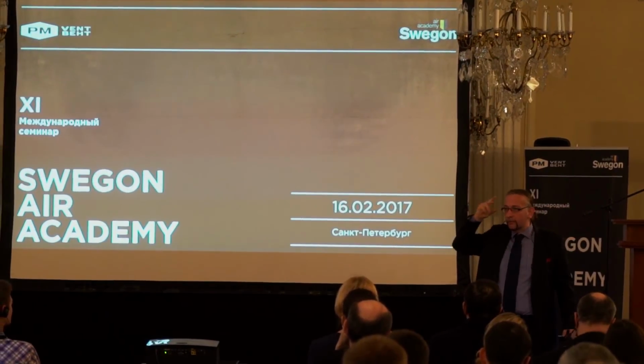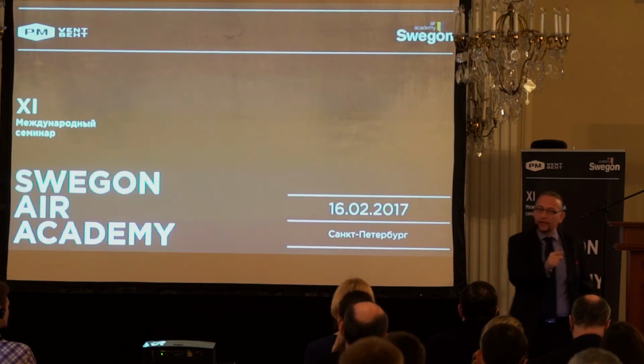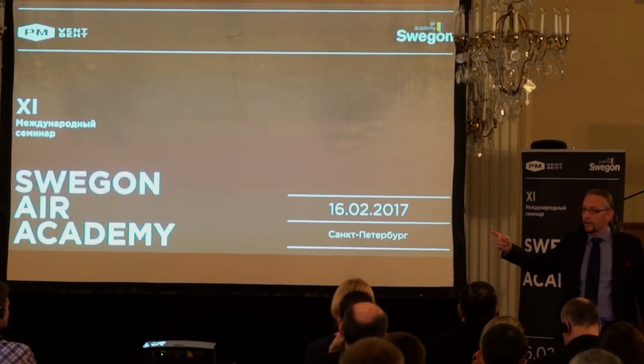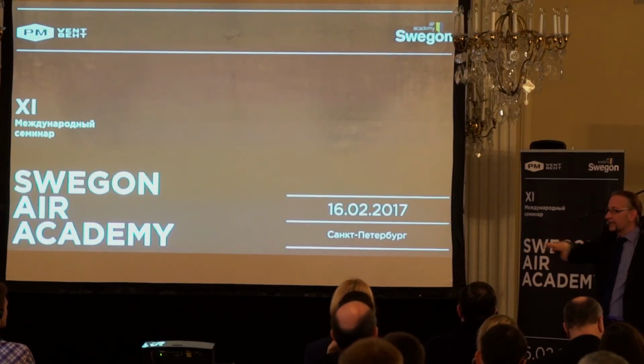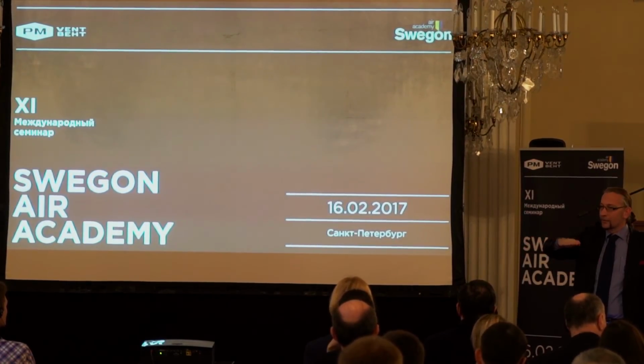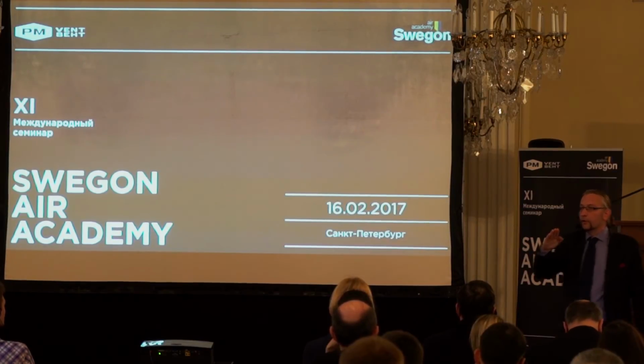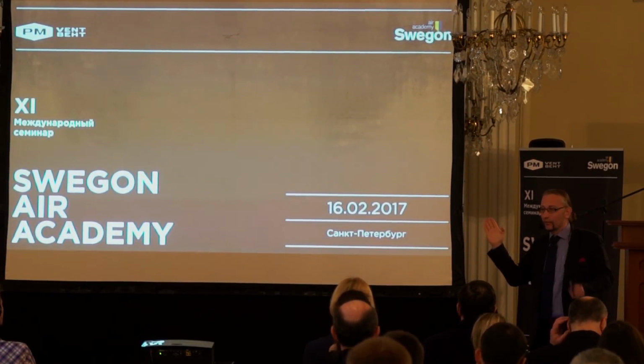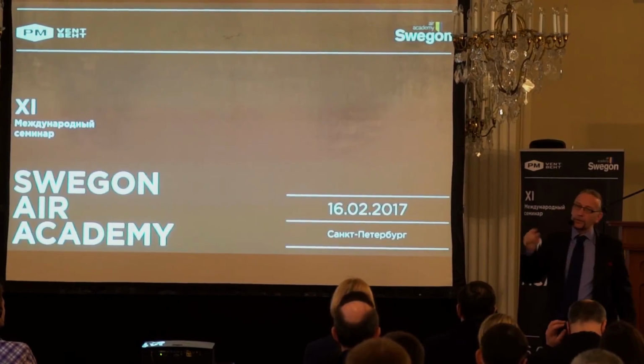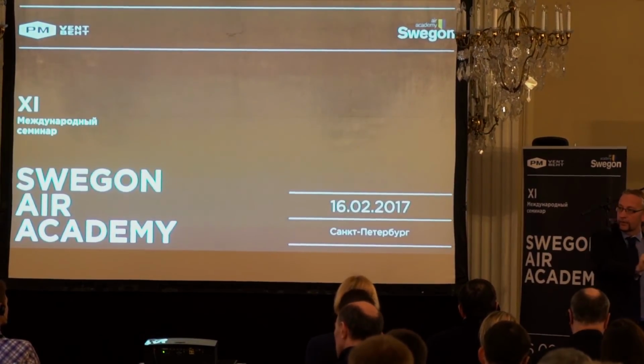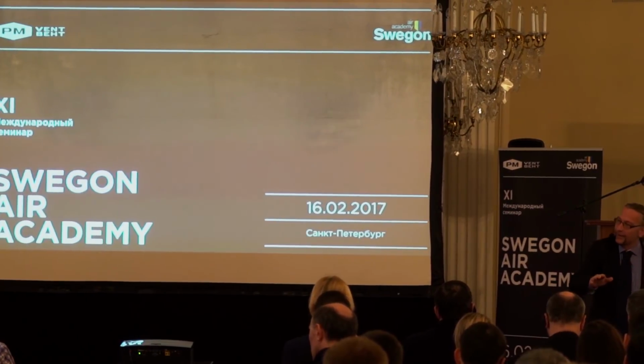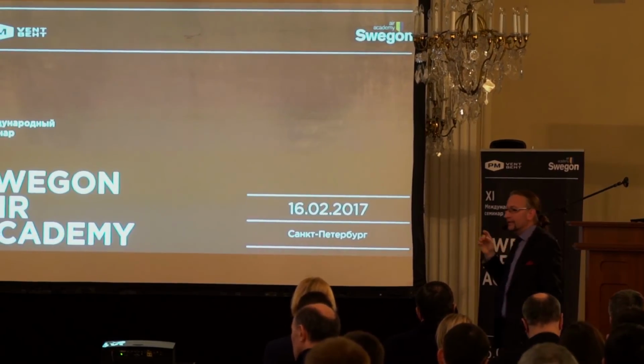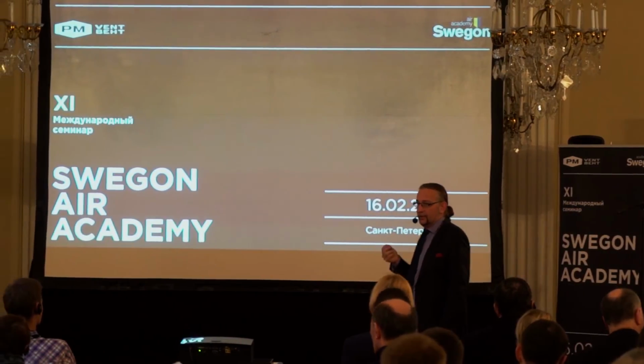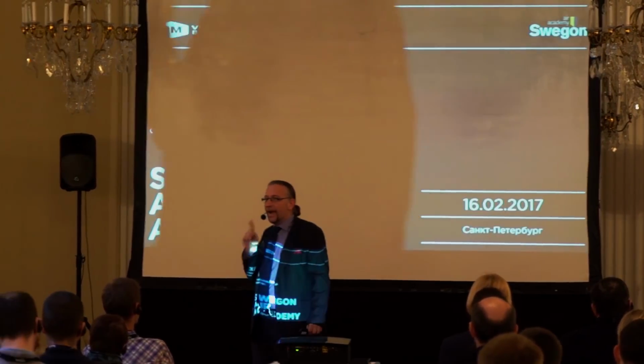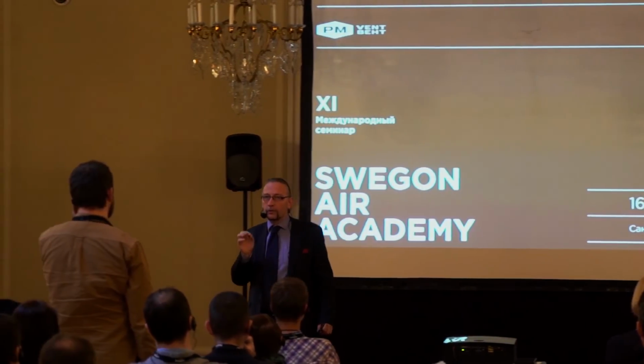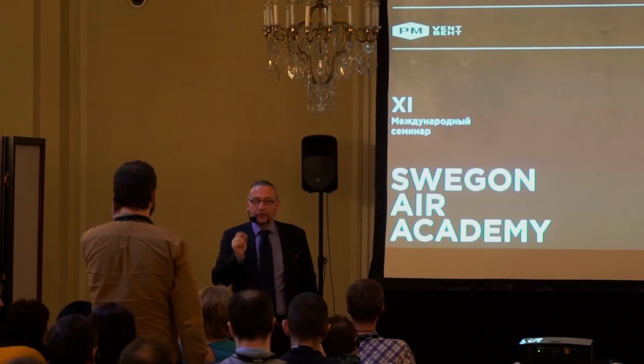Now what happens is the central brain, in this case the supervisor, will check all the positions of all the dampers. And it sees if the damper or the area that needs the most energy is only 50% open. What it will do, it will open the damper 100%, low pressure, and it will send a new pressure setpoint to the air handling unit. So the air handling unit will slow down, okay? So the difference is on the pressure control system. This is a big, big difference. The air handling unit is not running on constant pressure. The air handling unit is pressure controlled.